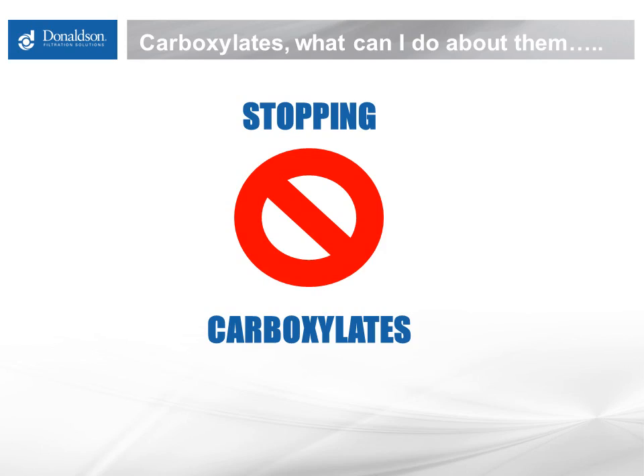Now we get to the important part of the webinar. We have talked briefly about what carboxylates are and how they are formed. Now let's discuss what you can do to minimize their impact on your operations. Metal carboxylates seem to be generated in very specific conditions: you need corrosion inhibitor, a salt — typically sodium — and high pH conditions to form them. This form of carboxylates could be generated by conditions at the end fuel user, but most likely they would be coming in with fuel in your normal delivery. In reality, it is difficult to prevent the delivery of fuel that may have a carboxylate issue.